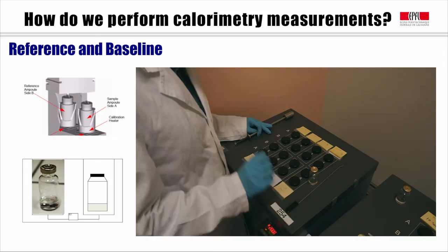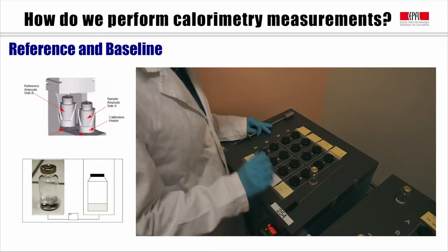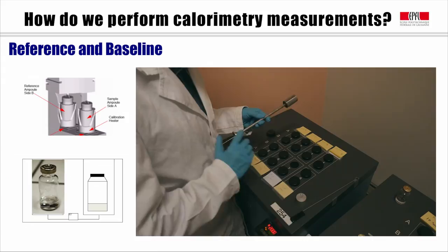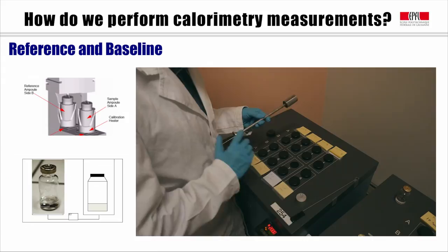Each channel has sample side and reference side, marked as A and B respectively. First of all, we open the plastic black lid. Use a steel hook to hang the heat sink plug out. Then we put the reference in, make sure it is going to the bottom sitting right on top of the sensor. After all this, we can place the plug back and close the lid.